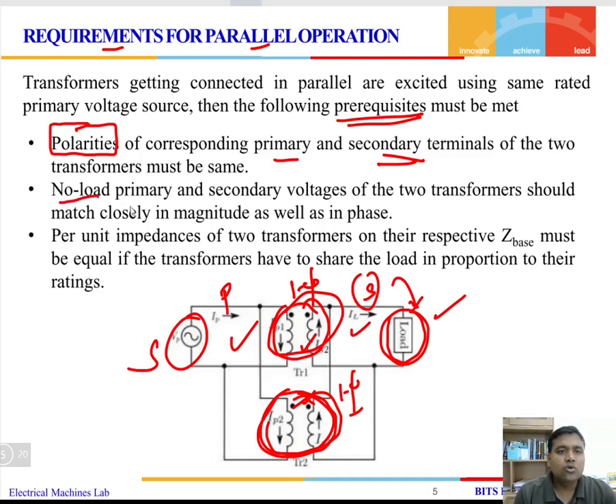Second, the no-load primary and secondary voltages of the two transformers should match closely in magnitude as well as in phase. So when load is not there, it is a no-load condition.